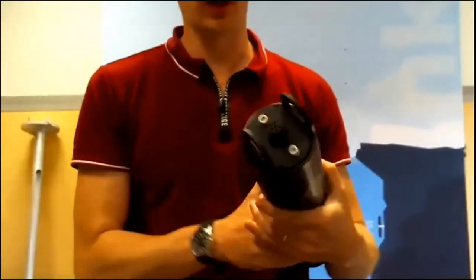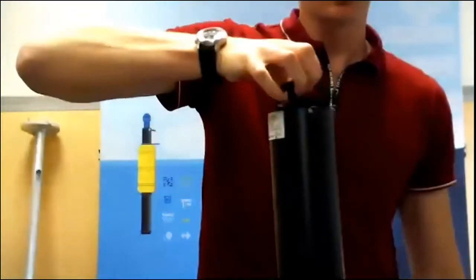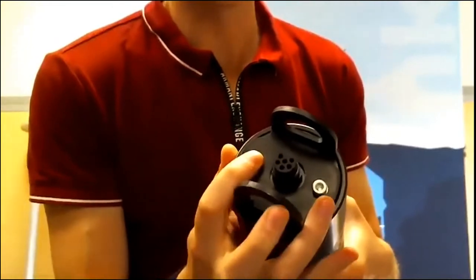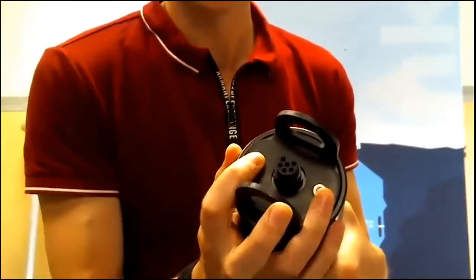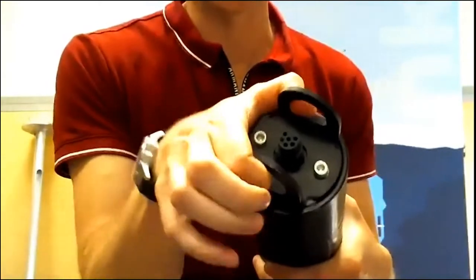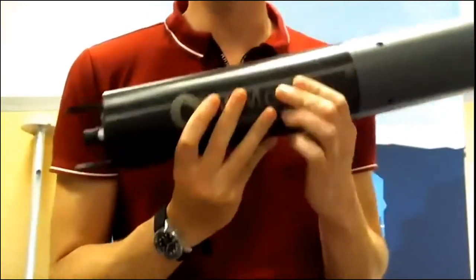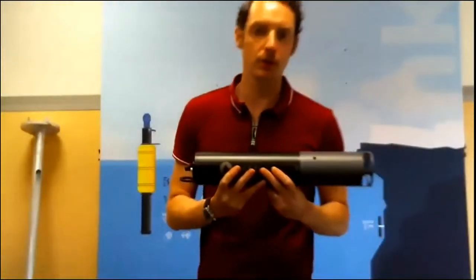On the back, you can either add or remove handles, which are ideal for profiling. Also, these 2 screws can be used for other types of implementation that I will show you afterwards. Please note that these are not plastic, but metallic handles, which makes them pretty rugged and tough. The main material of the WiMo is POM, which allows the WiMo to be deployed down to 250 meters depth.